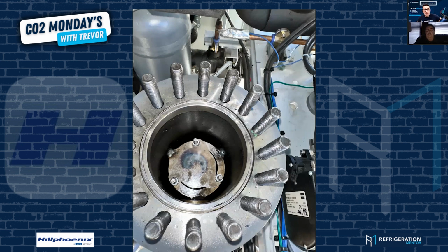I get that question asked all the time: how long does it take? In this scenario, there's only one oil separator, so you've got to pump down this whole rack. You're isolating the rack, pumping it down, and then isolating the separator, because the whole rack's off. You isolate the compressors and lock out the power so nothing turns back on. You change the alarm set points for your working time. Then you remove the pressure from the separator. You do not open it without removing it. It's no different than HFC systems. So you remove the pressure until it's down to 0, and then you take this off. Then you pull out the filter, change the filter, and change the gaskets.